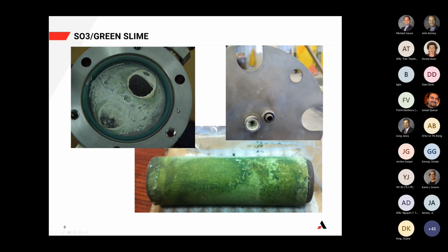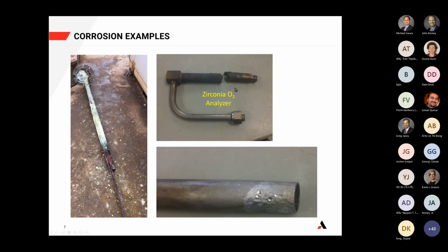Here are some examples of green slime. The upper left-hand corner one isn't from a SIMS unit, but it was a nice picture, so we thought we would show it. This is SO3 leaching the nickel and chromium out of stainless steel, which causes this lovely greenish color. Here we have some examples of corrosion from the SO3 combining with water to form H2SO4. You can see the dramatic pitting on the end of the probe tube here. Basically a completely destroyed zirconia oxygen sensor. And then a probe tube with the pitot tube and RTD, you can see it's completely covered and corroded. So these are some examples of what happens when your dew point is causing the SO3 to drop out on the wetted components.